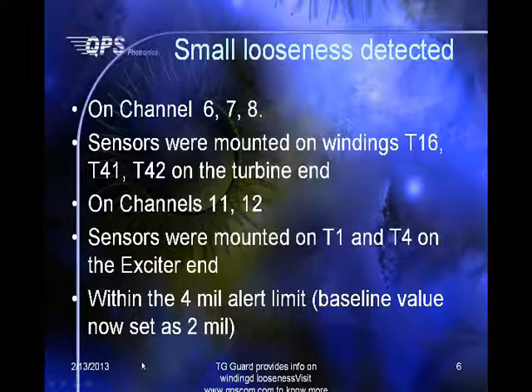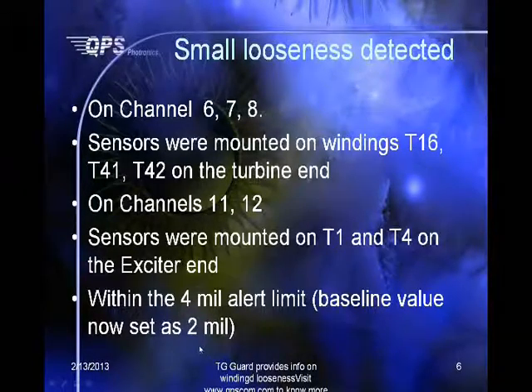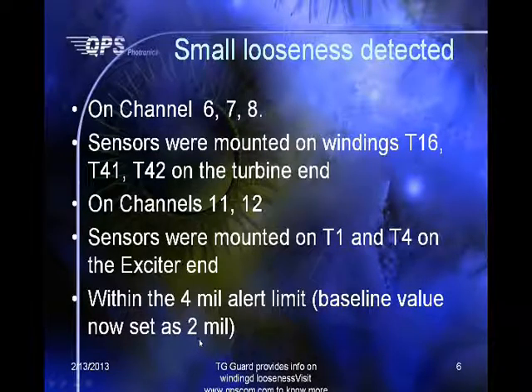But just to refresh all of us, the concept is we catch data first and then set it up as a reference, a baseline value. And then from there, we set an alert limit at 2 times that reference. So here, we set the baseline at 2 mil. By the way, that 2 mil is larger than most of the data you've seen today. So we are very conservative. And then the alarm should be set at 8 to 10 mil, at which we suggest that we should shut down the machine and do some maintenance right away.